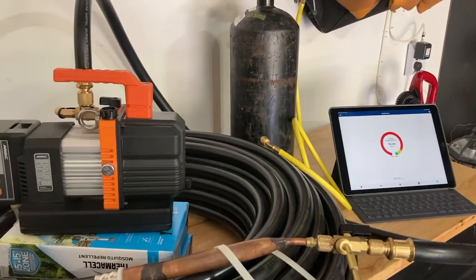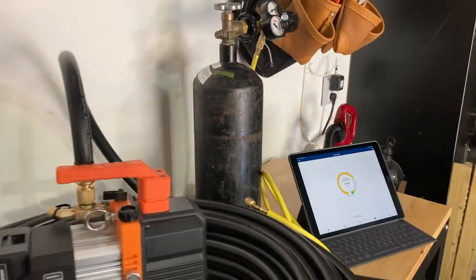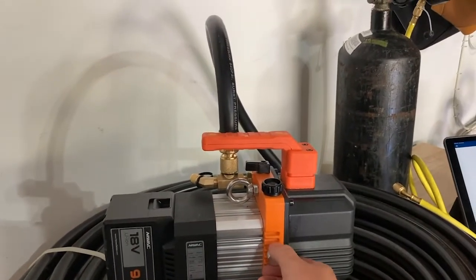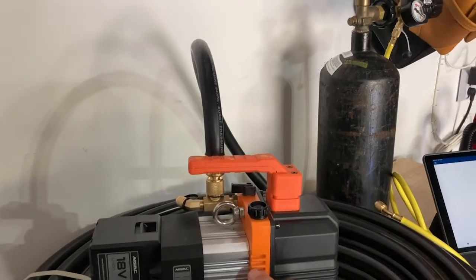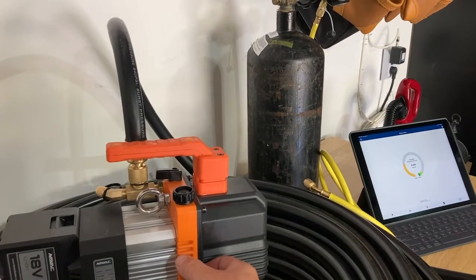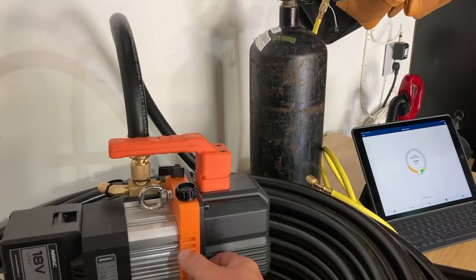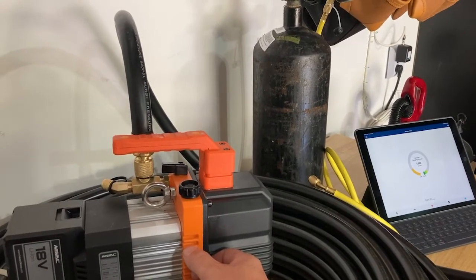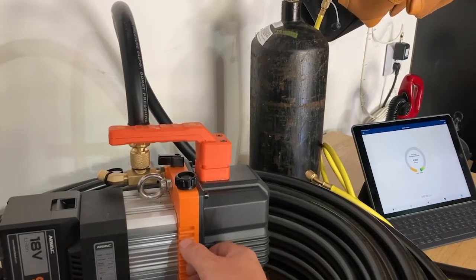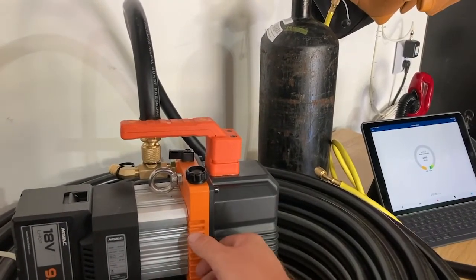We just hit 20,000 microns, so I'm going to open this gas ballast. What that allows is to save my oil between 20,000 and 2,000 microns — it basically allows a bypass. A small amount of moisture coming in through the pump is more attractive to that than it is to the oil, at least between 20,000 and 2,000 microns, and it allows it to grab that moisture before it contaminates the oil.